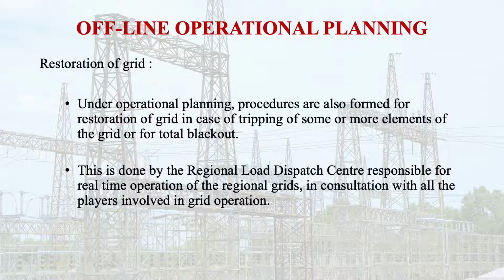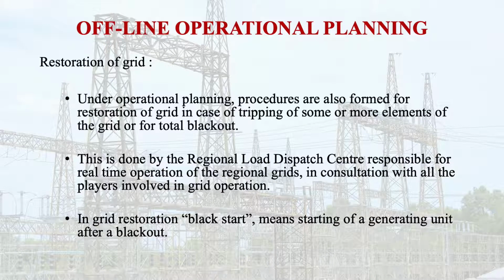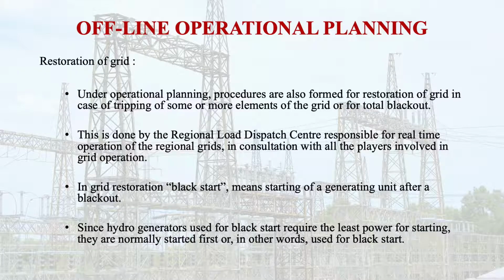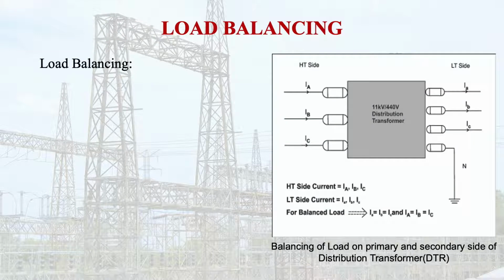So in consultation with all the players involved in the grid operation, one of the points involved in grid restoration is black start, which means starting of generating units after the blackout. And since hydro generators require the least power for starting, they are normally started first, or in other words used for black start. Now I'm going to define the load balancing.